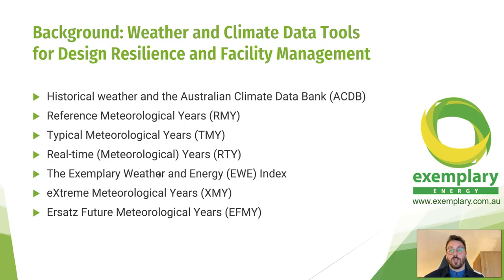And so in order to demonstrate energy efficiency compliance, both residential and commercial applications use what we call the representative meteorological year or typical meteorological year. They are hourly datasets of a range of climate and weather elements such as dry bulb temperature, humidity, wind speed and direction, and solar radiation that have been compiled to represent the typical hourly profile of weather for 12 months, or a period of 8,760 hours.